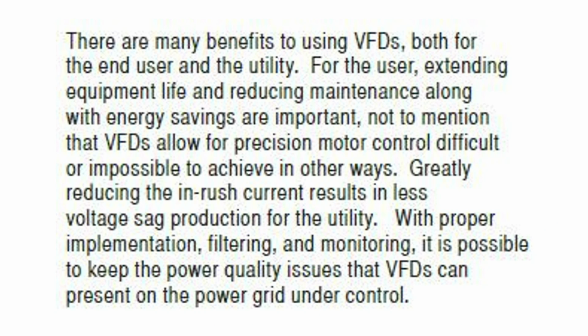So, inrush current, when you go from across the line start motors to either soft starts or variable speed drives, not a really big difference because the drive will do soft starts. Only difference is the soft start can't change the speed of the motor. But preventing that inrush current will prevent voltage dips.